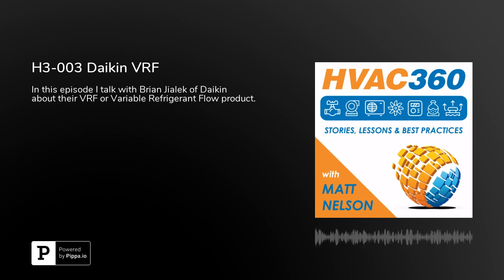Oh, okay. Excellent. All right, so what else haven't we talked about? Several different things that we're launching in other areas, other markets. For cold weather applications, we've got an ultra-low ambient system that's VRV based. You have an additional cabinet on the side of it that adds another loop of refrigerant flow, similar to a cascade sort of refrigerant flow, and that achieves a lower discharge temperature, a lower ambient temperature at which you can mount these systems outdoors. So in the low ambient situation, you can have the units mounted outdoors to as low as minus 13F. So it's a very good application. Those are areas that heat pumps typically don't travel into in most cases. So very low ambient situations.